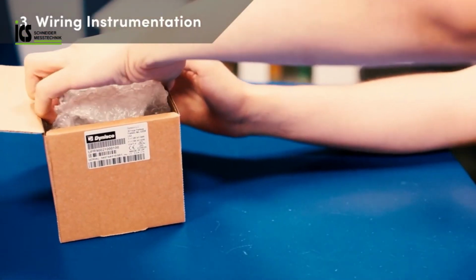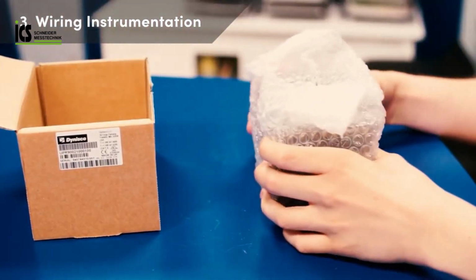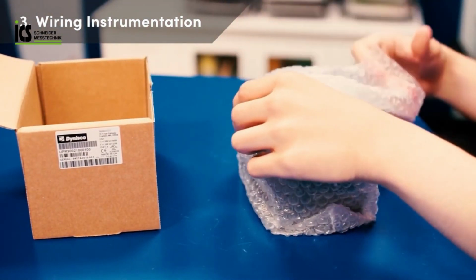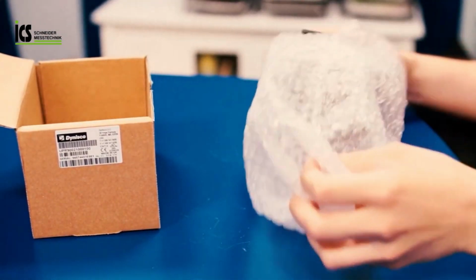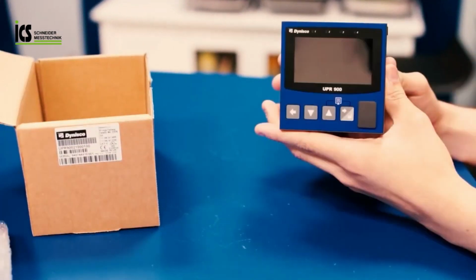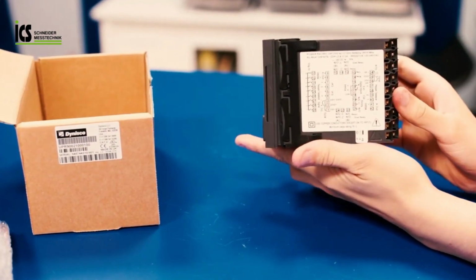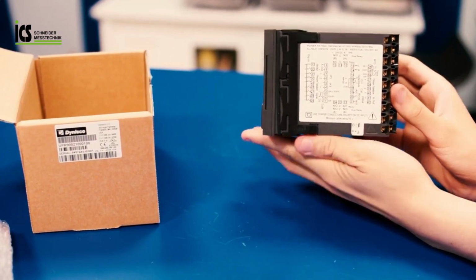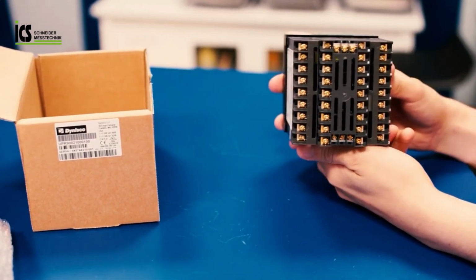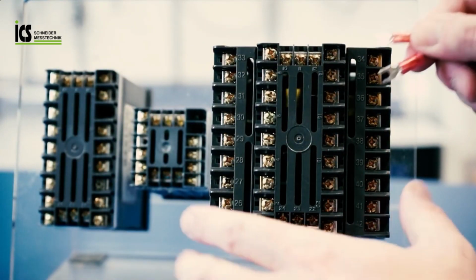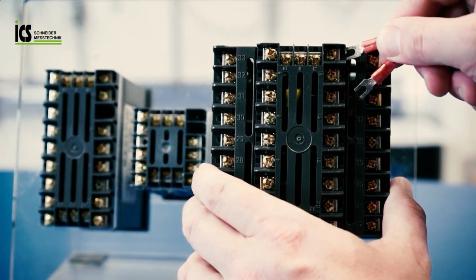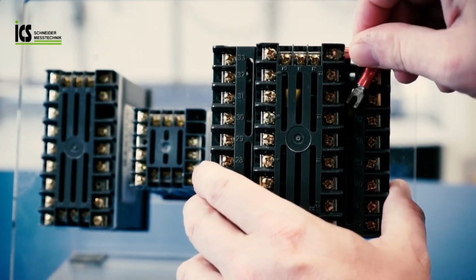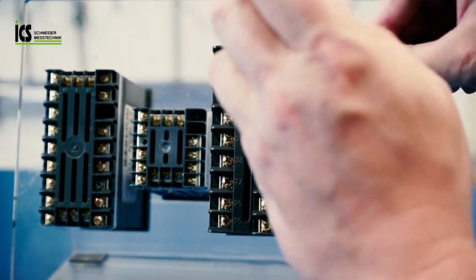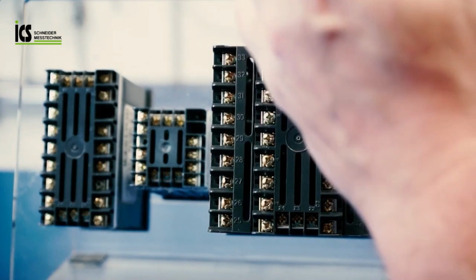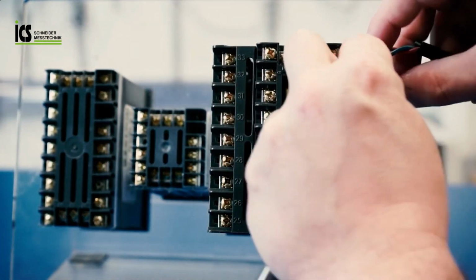Next, the selected indication device or controller is removed from the box and examined for damage. In the unlikely event damage is discovered, Dynisco recommends that the customer document the damage and then return the instrument to Dynisco for evaluation. Once cleared for use, the instrument can be wired for main power input on terminals 13 and 14, provided the instrument has been mounted in a safe enclosure and a qualified electrician is bringing power to the instrument per the documented requirements. Please review the operator's manual for further details.